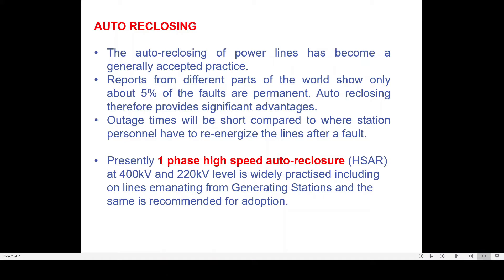The next case may be single phase and three phase autoreclosure. These are generally implemented where transmission lines emanate from a substation and terminate into some industry, such as a mining industry. In that case, if the fault occurs for the first time — suppose in R phase to ground — then only the R phase breaker will open, and after a sufficient time interval called the dead time, this pole will be reclosed.